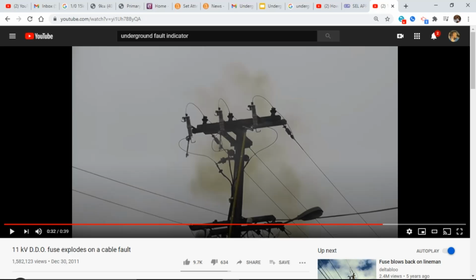So obviously, did they do that here? No. Now, in the olden days, and this picture does look kind of old, even though it does look like a new stick. That's old framing. Look at that insulator. Yeah. In the old days, before you had high pot sticks and all that cool equipment that we've got now, this was the typical means of finding out if you had bad spans. So you would open the first transformer, close a fuse. If the fuse held, you'd open the next transformer and close, open the next and close until you blew a fuse.